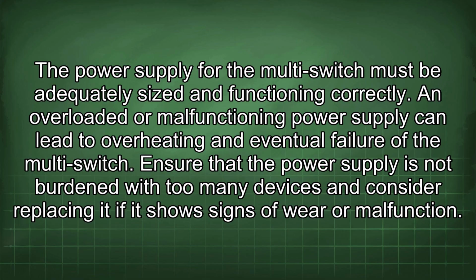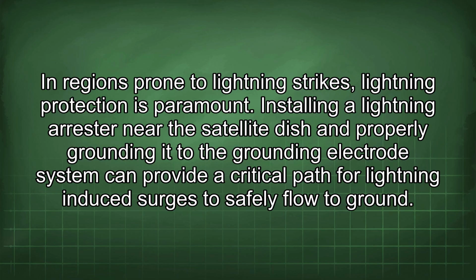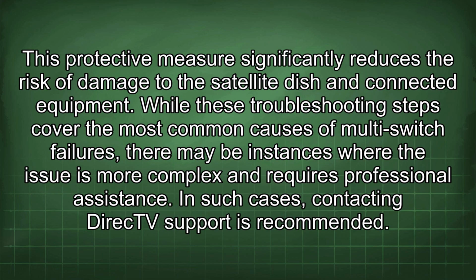In regions prone to lightning strikes, lightning protection is paramount. Installing a lightning arrestor near the satellite dish and properly grounding it to the grounding electrode system can provide a critical path for lightning-induced surges to safely flow to ground. This protective measure significantly reduces the risk of damage to the satellite dish and connected equipment.